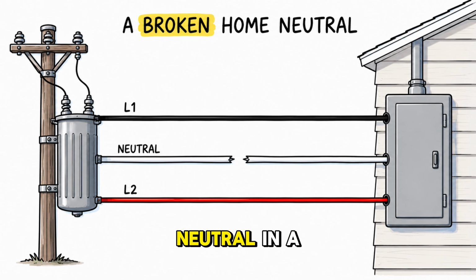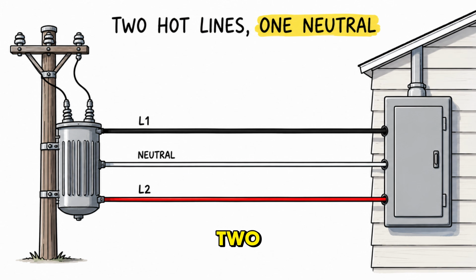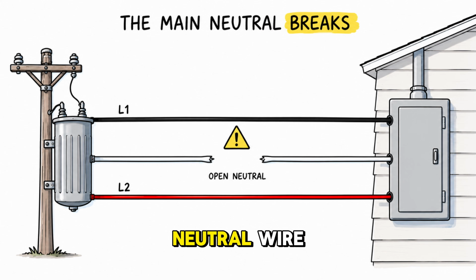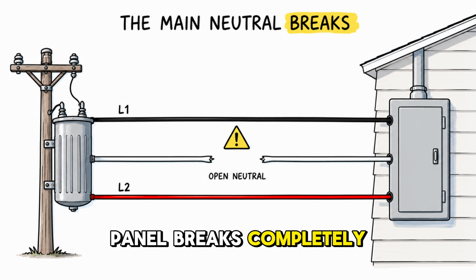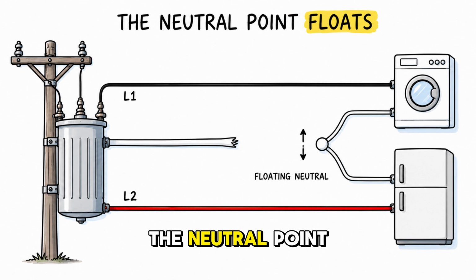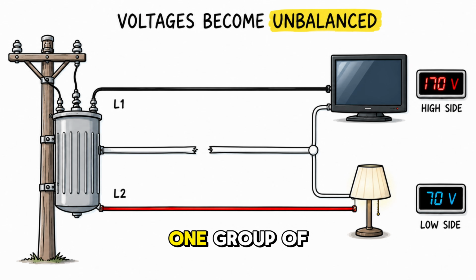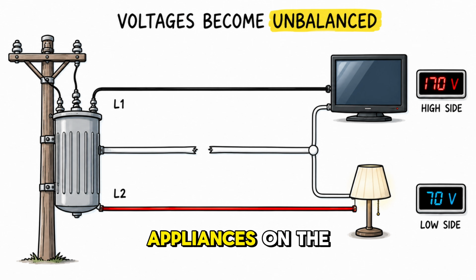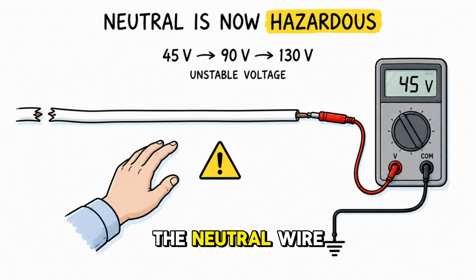The second condition is a broken neutral in a standard residential service. Your home has 2 live wires sharing one neutral path. When the main neutral wire between the transformer outside and your panel breaks completely, something catastrophic happens. The neutral point is no longer held safely at 0 volts by the transformer connection. Instead, it floats to a completely new voltage, determined by whatever appliances happen to be turned on at that moment. In this exact situation, one group of circuits may spike up to 170 volts, while another group drops down to 70 volts. Appliances on the high voltage side burn out instantly. Appliances on the low side stop working. Most importantly, the neutral wire in your home is now sitting at a hazardous voltage that changes from moment to moment. Touching it delivers a severe shock.